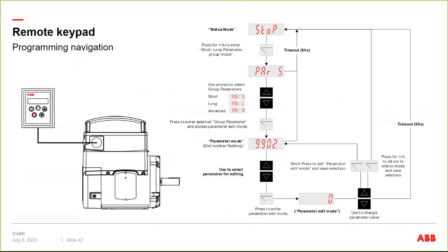From a programming standpoint, I just want to show what it looks like when you get into the keypad. You've got a short, long, and advanced parameter group. The short group is for just setting up accel, decel ramps, etc. Advanced is for your motor parameters, and the long is all the parameters. Now, I would tell you, when I set up a drive, I just go to the long list. There's only 40 parameters in the entire drive. So it's not like you're wading through 300 parameters that need to be divided into different groups. So that's a pretty easy drive to set up and program from that standpoint.